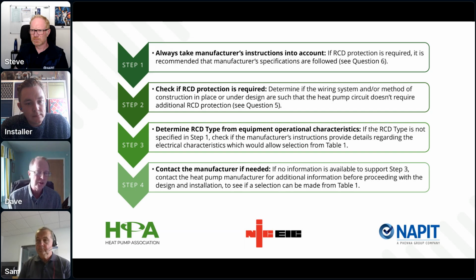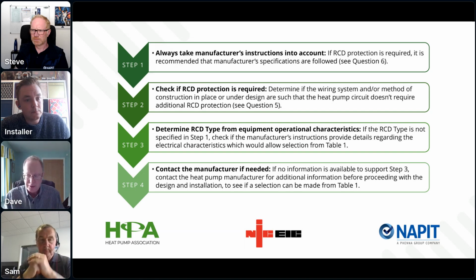One reason, of course, is that houses are different, buildings are different, and the manufacturer themselves can't know the electrical installation onto which a heat pump is going to be installed, and can't account for every single variable within that. That becomes the job of the installer and the electrician, for example. So you need to think about more than just blindly following instructions sometimes, but also it's sometimes the case that manufacturer's instructions are not as specific as you might expect them to be.